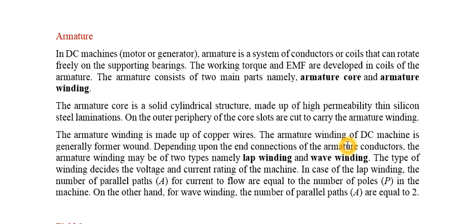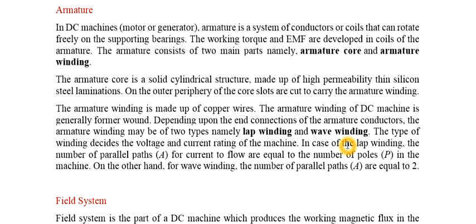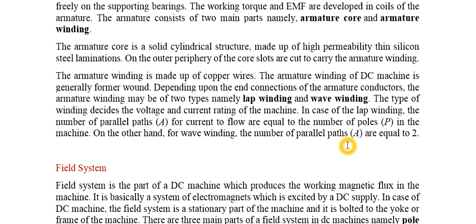Laminations are used to reduce eddy current losses. On the outer periphery of the core, slots carry the armature winding, which is made of copper. This winding is former-wound — meaning the winding is prepared first and then placed directly into the armature slots. Depending on the end connections of the armature conductors, there are two types of windings: lap winding and wave winding.